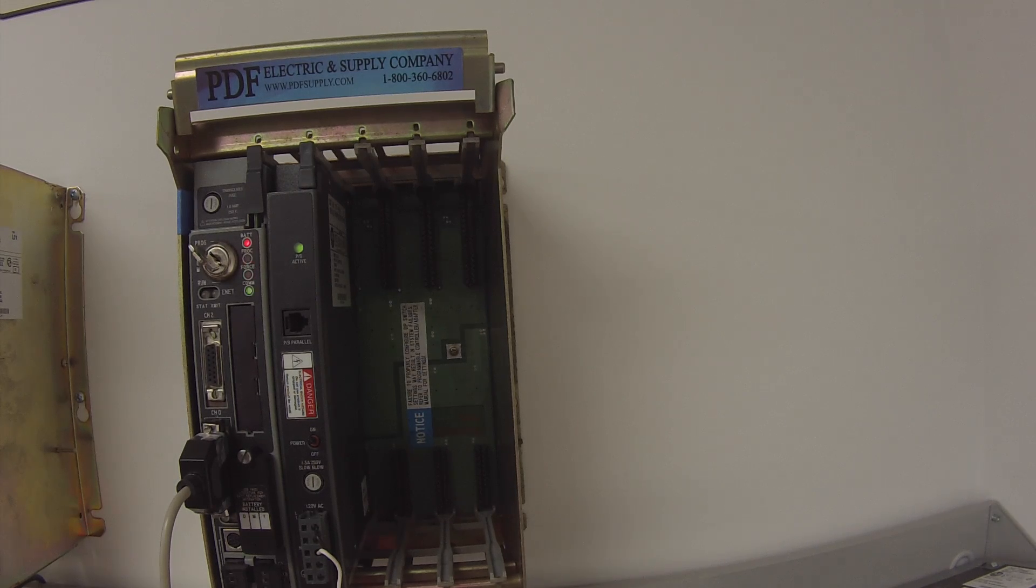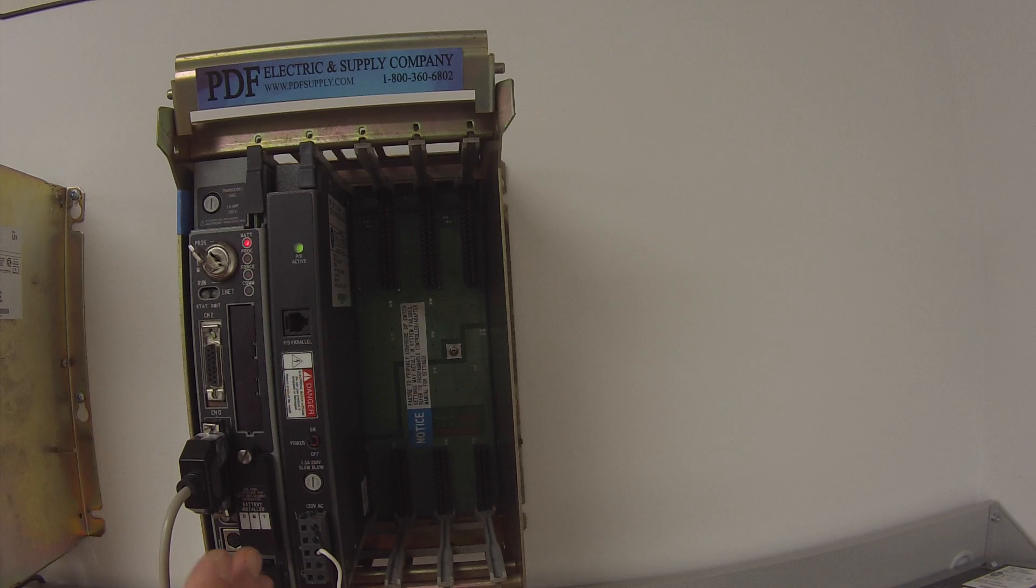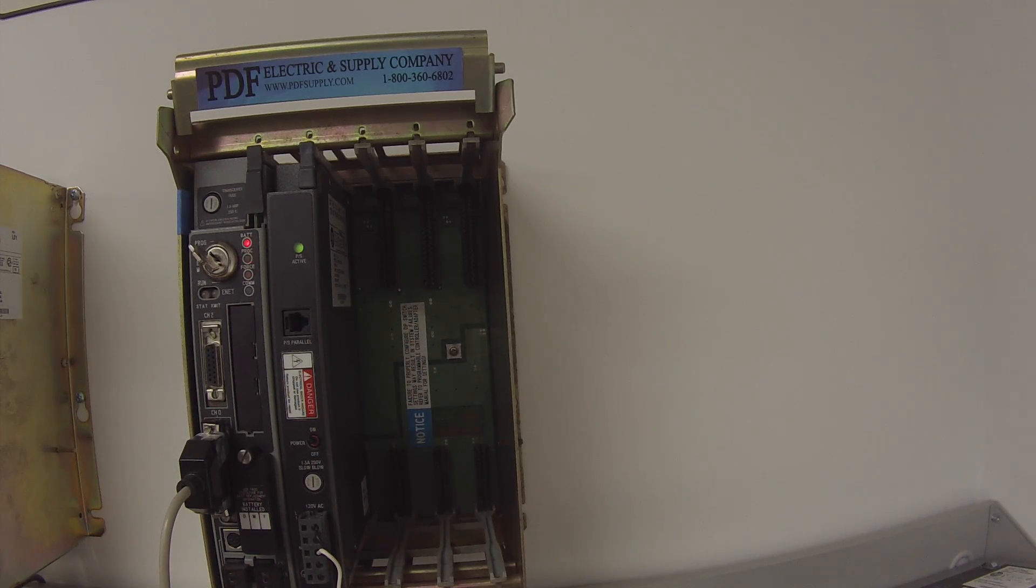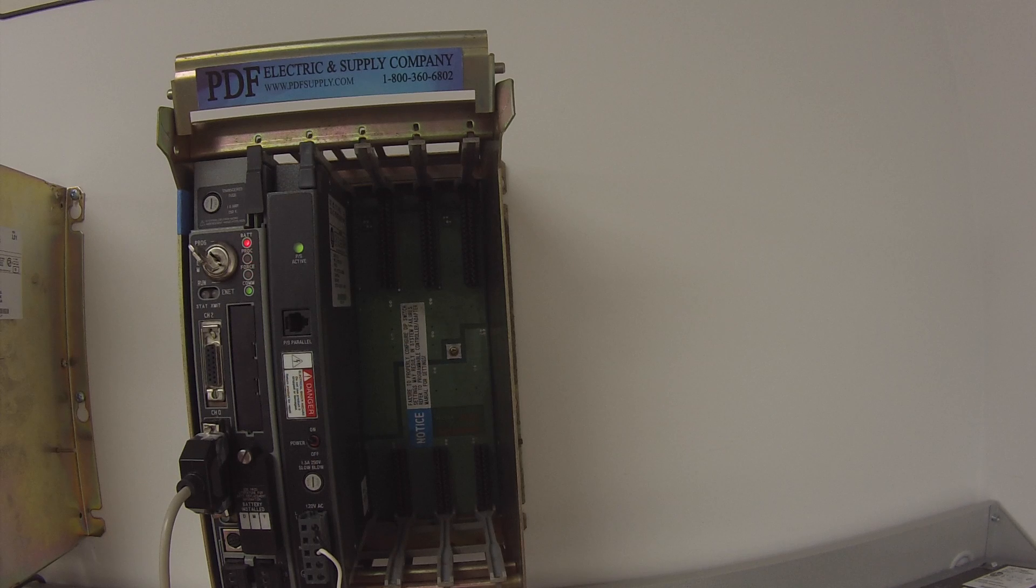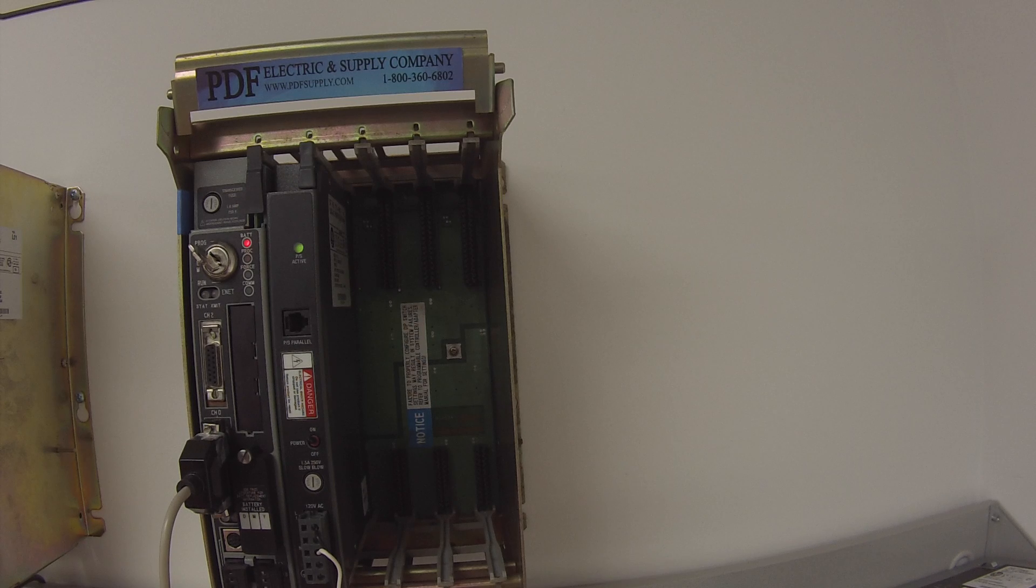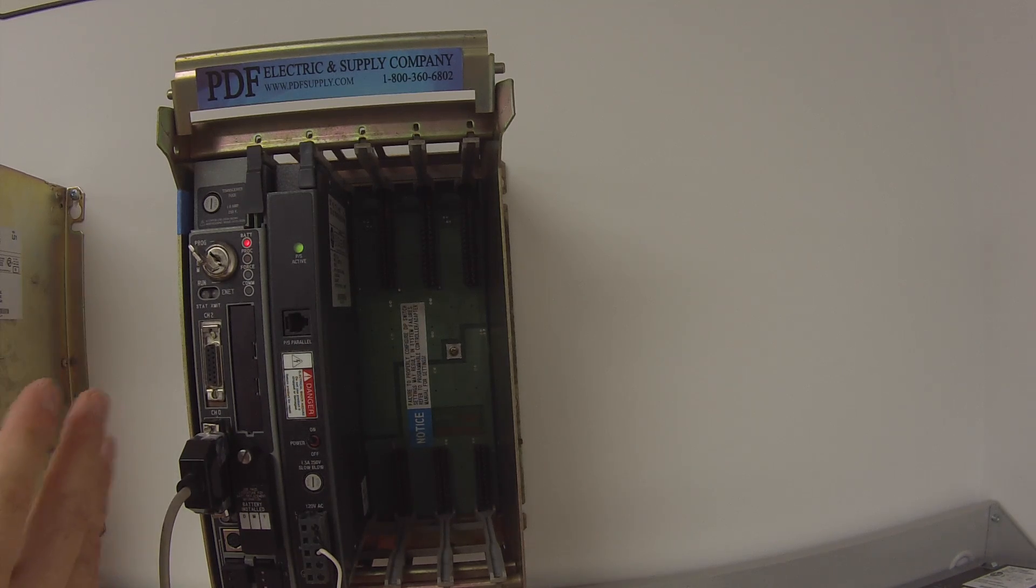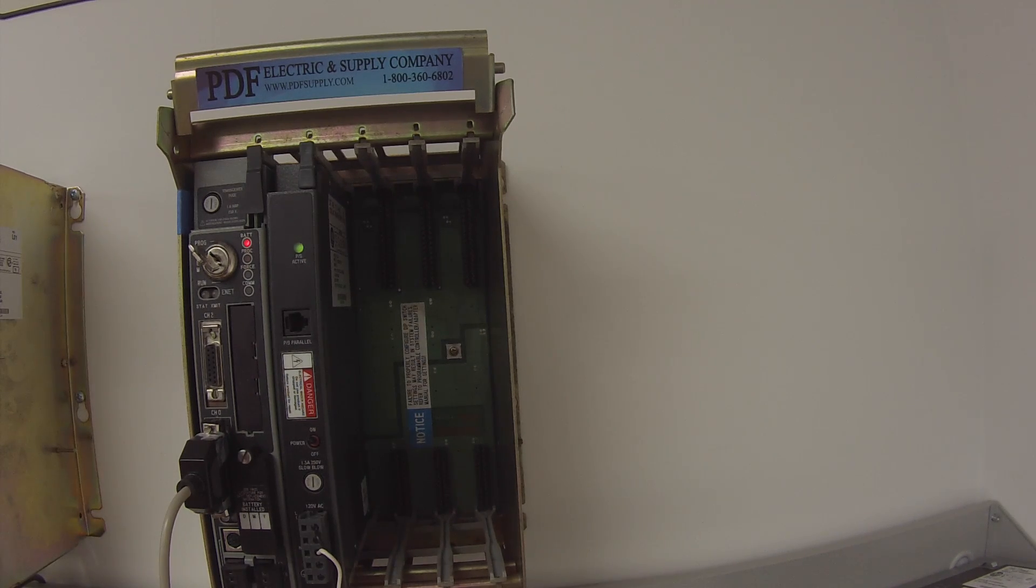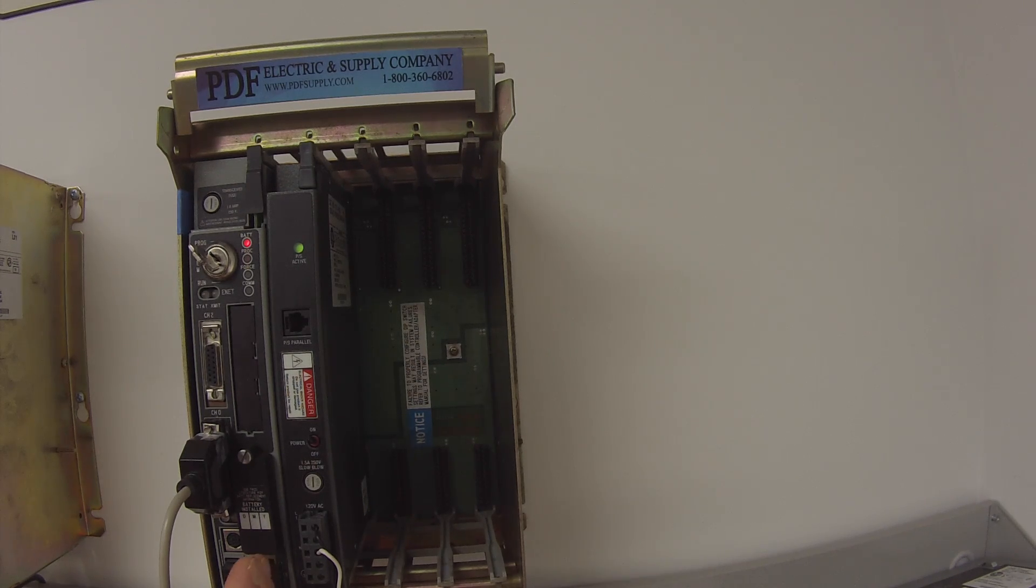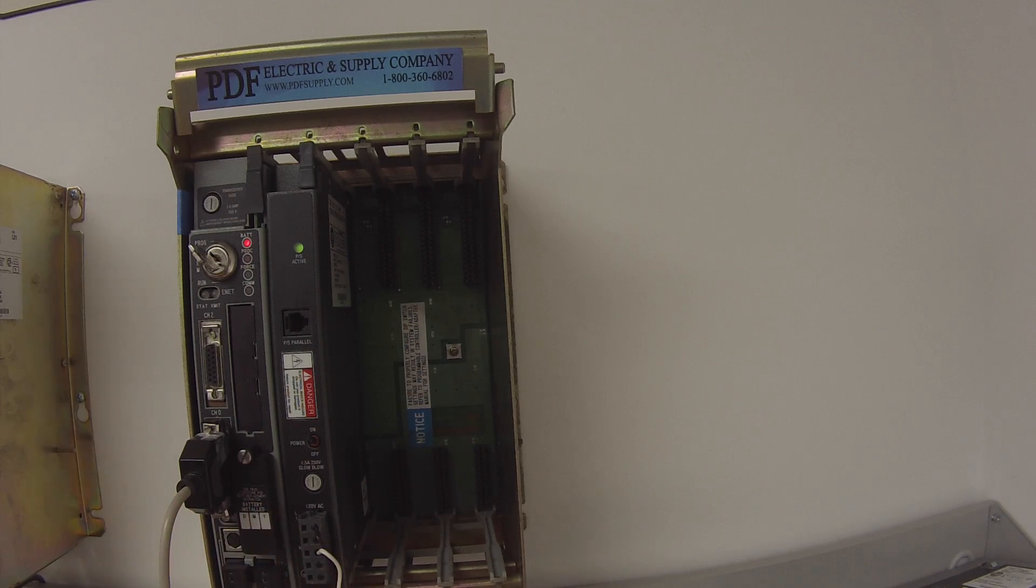Very important for all processors to make sure that you have a good working battery, a tested battery that you're sure is working good. All processors. In this particular case, the L20E, when you establish this IP address like I just have, it will sometimes ask you to power cycle. If you power cycle and the battery's not working, you'll likely lose that IP address during the test. Just please, always make sure that you have a good working battery for these tests.